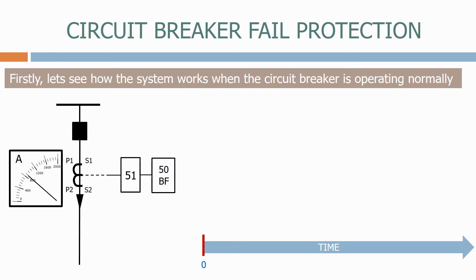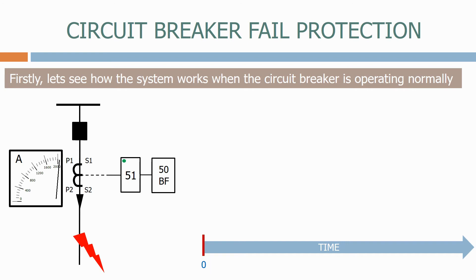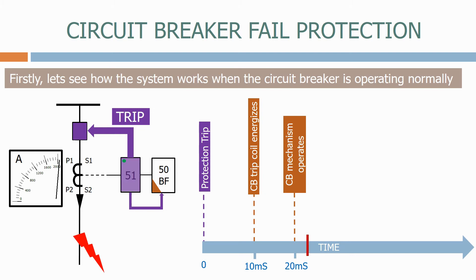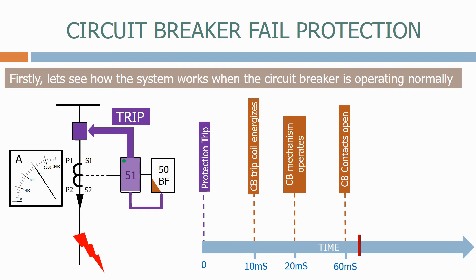Let's now apply a fault on the feeder. Once the current gets above a certain threshold, the protection relay will energise the circuit breaker trip coil. After a short time delay, the circuit breaker mechanism will operate. The circuit breaker contacts will open and eventually the current will stop flowing.